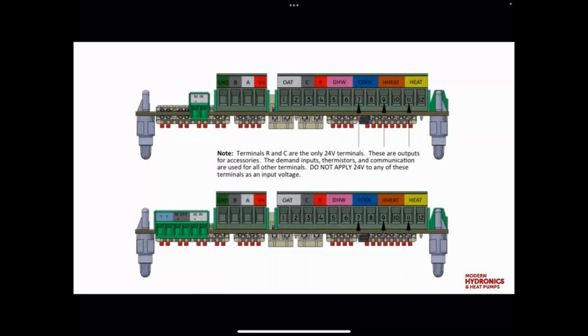Yeah, and too, a point that's really good about dual fuel looking forward is when you get into things like off-peak, on-peak electrical rates, there may be times when the boiler might be less expensive to operate than the heat pump, and this could accommodate that. I also think about power outages. The power you would need to run the backup boiler in comparison to the power needed to run the heat pump, you could run the backup boiler on a very small portable generator. So there's definitely advantages to that dual fuel approach, and certainly in retrofits, many times you're going to have a boiler that's already installed. The heat pump comes into the picture. The intent is to make the heat pump the primary heat source, but retaining that existing boiler and making it as simple as just piping it to the back of the unit makes it very easy in the field for the contractor.